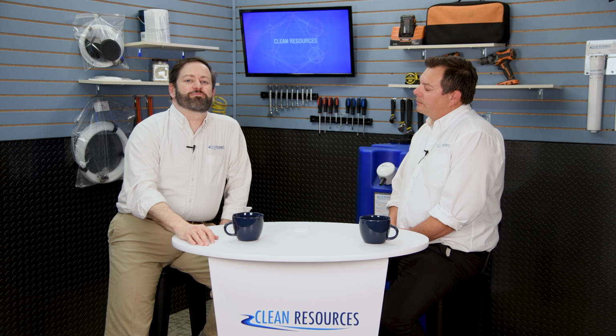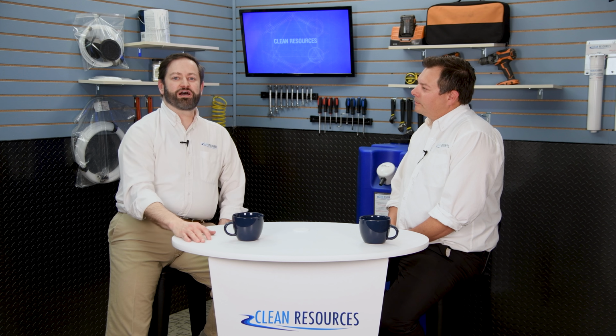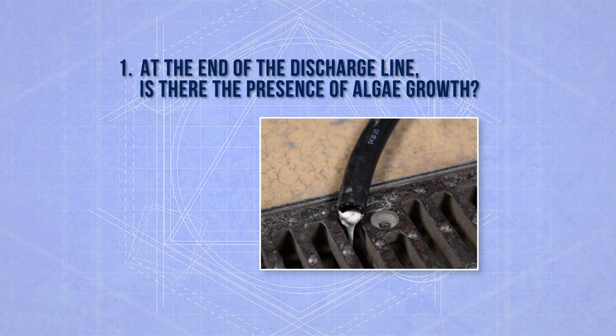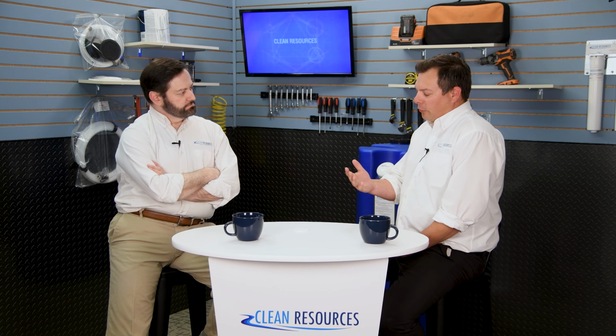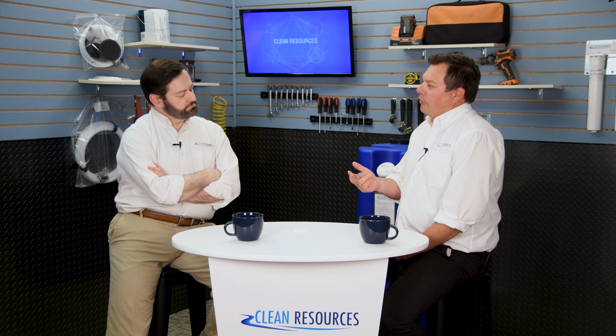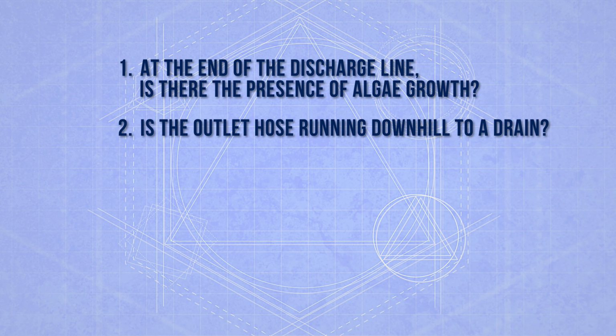So let's go over some of the most common scenarios and talk through how to resolve each one. Jerry, what I would first look for is to see if there's any algae growth in the end of the discharge hose. That will be a key contributing factor to restrict the flow. The second thing that I would check is, is the discharge hose running freely and only downhill to a drain?